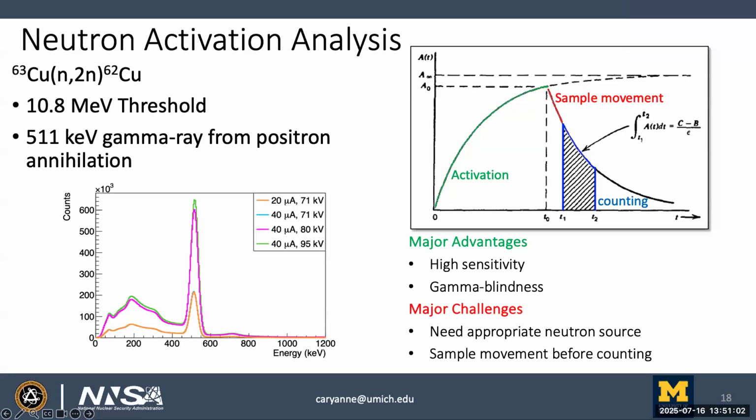There's another question about applications. How are neutron detectors able to operate inside nuclear reactors, considering the extreme conditions such as pressure and radiation damage? So like I said, a lot of times you can use neutron activation foils because those are kind of immune to that. And then you have a rabbit system to move the activation foil to a detector, to basically count it with a detector that's in a remote location.